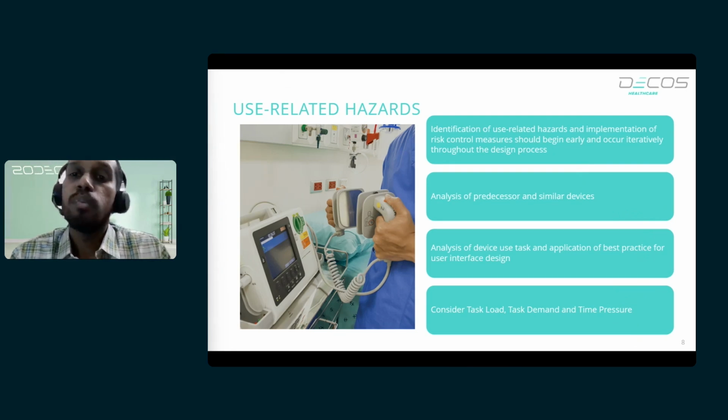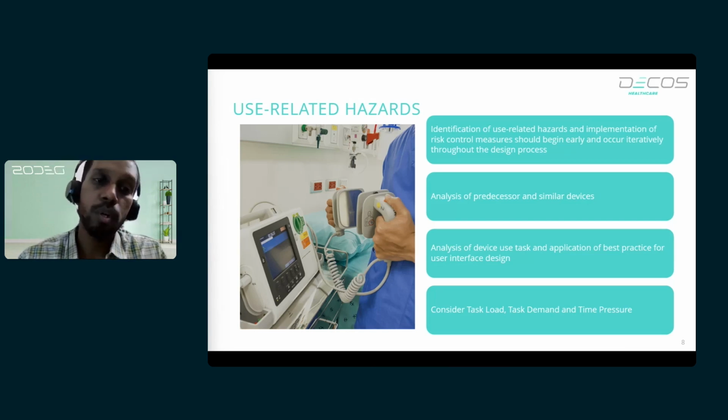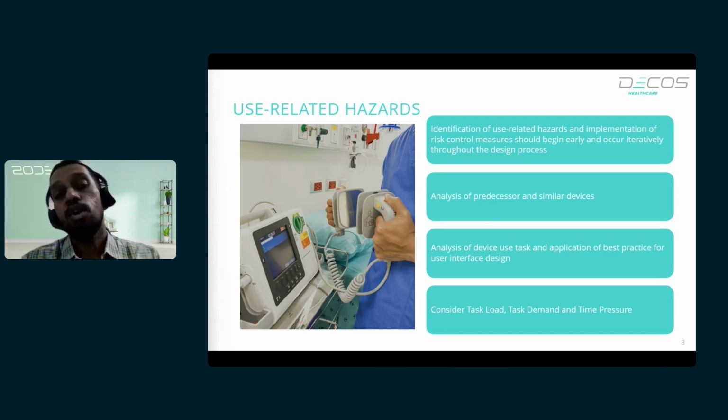For this, we can perform various interviews with the clinicians or the real-time users who are going to work on the device. It can be a layperson, a clinician, or some support staff who work along with the clinicians while performing this action. So we need to perform contextual interviews with the users, or perform formative and summative observational studies to observe how the device is working, and in what scenarios and environmental conditions the device fails to perform its intended use. Everything would be taken into consideration.